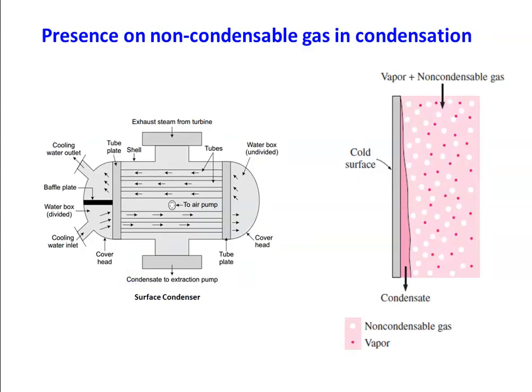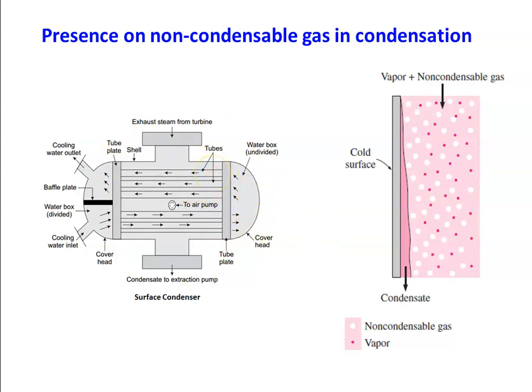The next topic is the presence of non-condensable gas in the condensation process. In a condenser, steam from the turbine flows on the shell side and condensate flows downward, removed by a condensate extraction pump. Cooling water flows through the tubes. The condenser operates at a pressure lower than atmospheric pressure — a vacuum — so that the turbine work output is maximized.